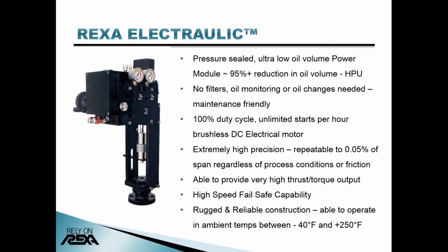All models are 100% duty cycle through the use of brushless stepper or servo motors. These units are high precision and repeatable to 0.05% of span. Our modular design allows for very high thrust and torque output with high-speed fail-safe options. Operating temperature range is minus 40F to 250F without performance degradation. And having passed rigorous testing for the US Navy, REXA actuators are unmatched when it comes to being rugged and reliable.